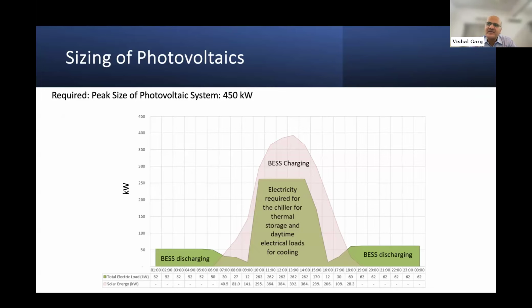So here you see what our thinking is: if this kind of a system is deployed to a residential complex, then there would be a possibility that we have less capex because of the reduction in chiller. We have less opex because it is efficient, and the photovoltaic based energy is much cheaper than the grid-based electricity in the night time. So it can save cost even when there is a loss of efficiency in charging and then discharging, as well as a loss of efficiency at the chiller, because it is delivering at -5 degrees centigrade. Even considering all those losses, because of the better tariff coming from the solar energy, in the end it will give lower OPEX and it will be 100% green.